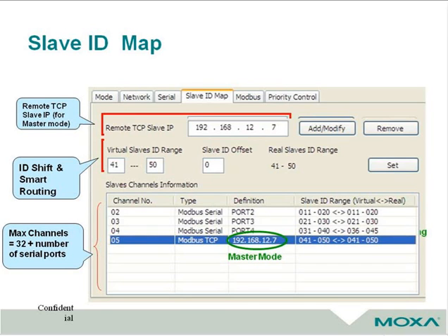Moving on to how slave IDs are mapped on the MGate MB3000 series. When a Modbus master requests information from a Modbus slave, the request is addressed to the desired slave's ID, which must be unique on the network. If this is not properly addressed, a request sent to the slave ID will receive more than one response, causing a communication error.